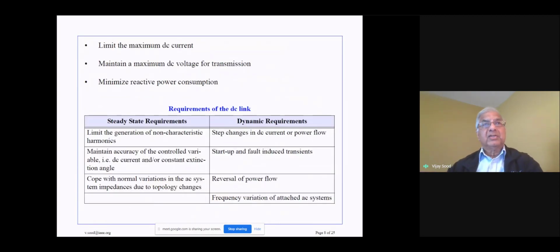So here are the primary functions for the DC controllers. First, they must limit the maximum DC current. This is because the valves have a very low thermal inertia. So any kind of excessive current in the valves could be dangerous for the valves. So we must limit the maximum DC current. Typically, this could be limited to maybe about 1.2 per unit value. But beyond that, the valves do not like having too much current going through them.